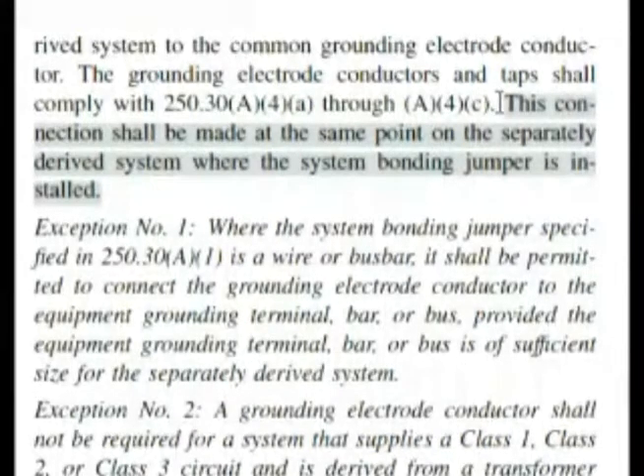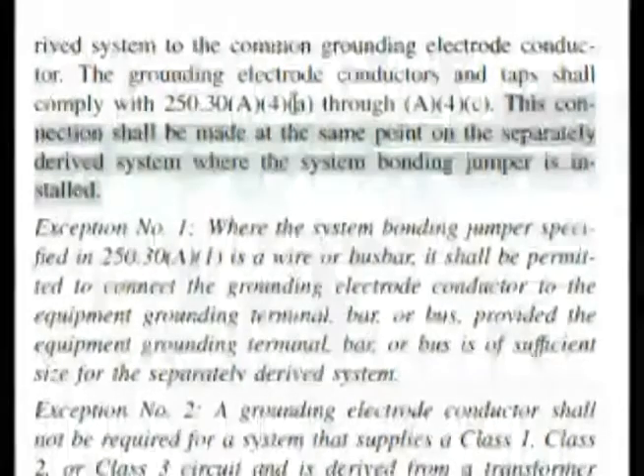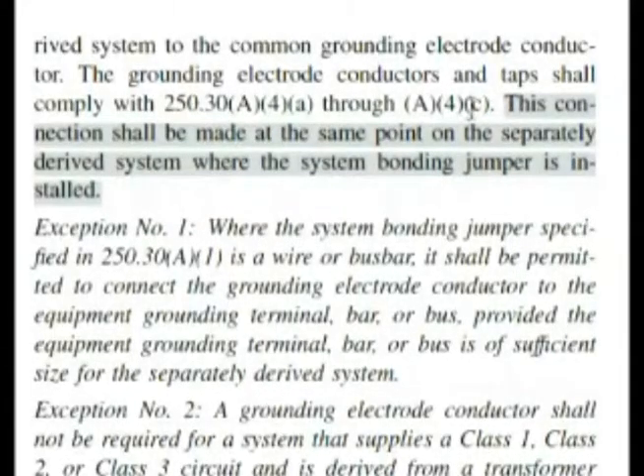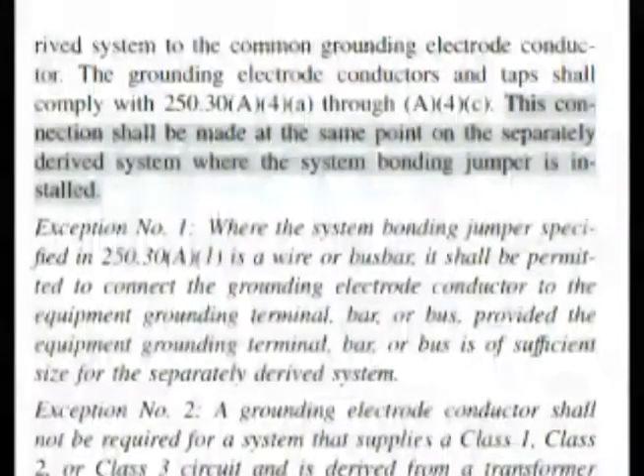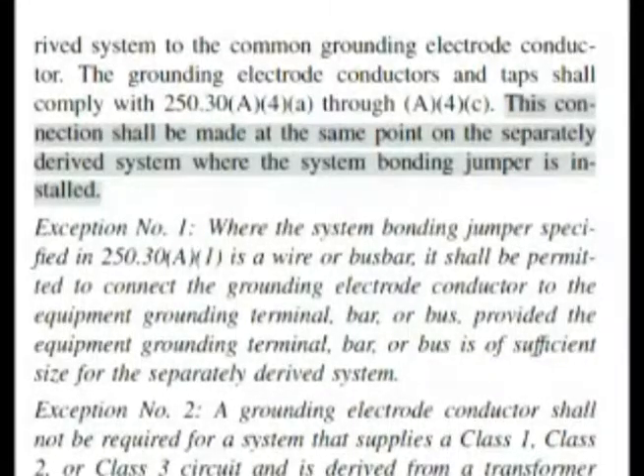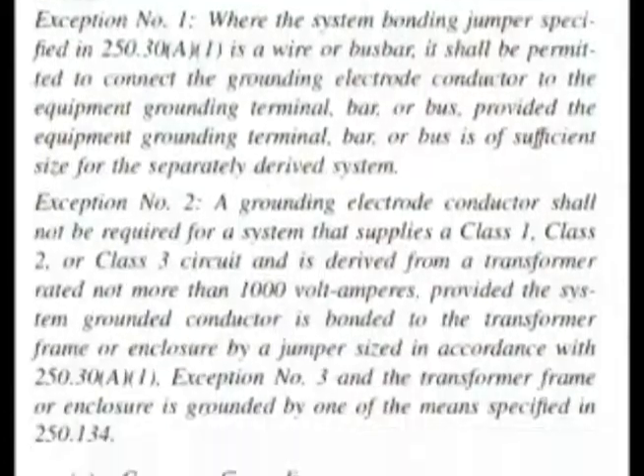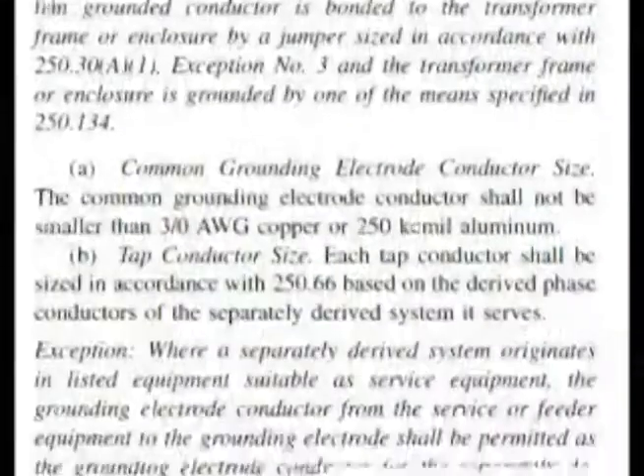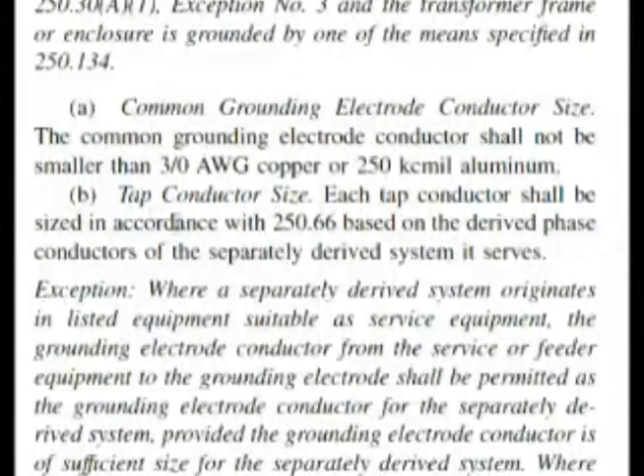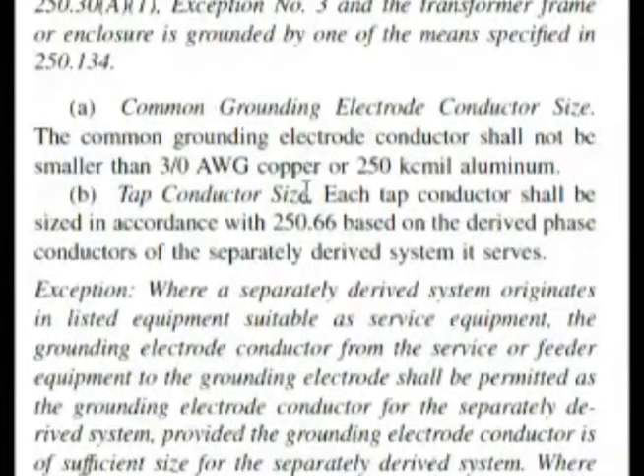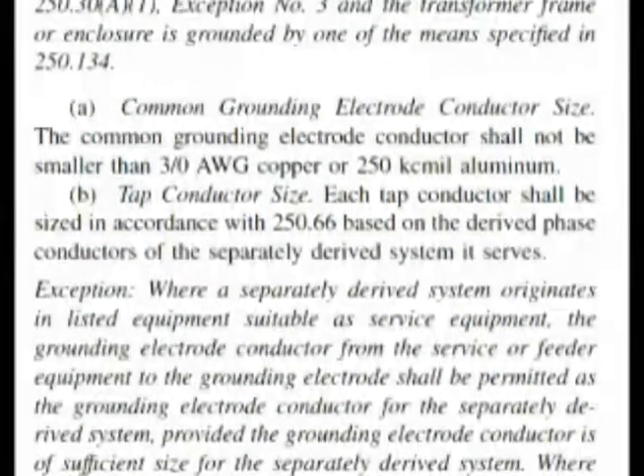Here we are at the top of the next column, continuing in section 250.30(A)(4). It says these shall comply with (A)(4)(a) through (A)(4)(c). That is going to be just below, because we have some exceptions. Scrolling down, we see: A — common grounding electrode conductor size; B — tap conductor size. These are the bold headings in italics, so you would read to see if that matched what we wanted. Let's go down to C.